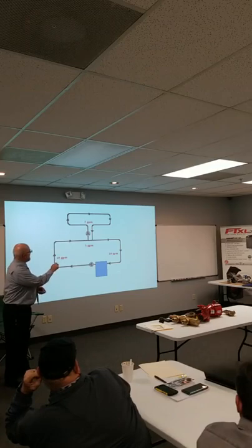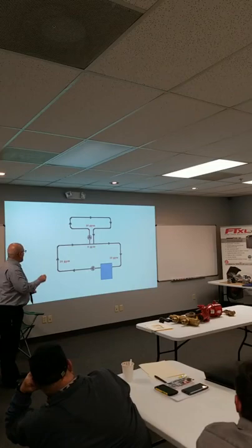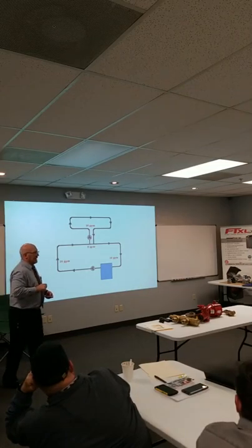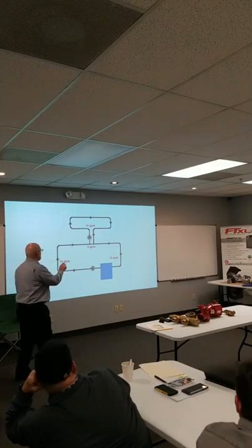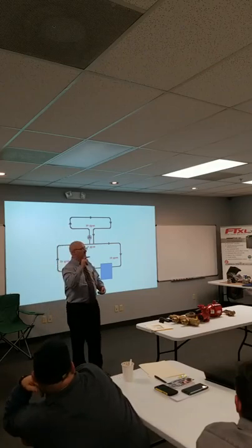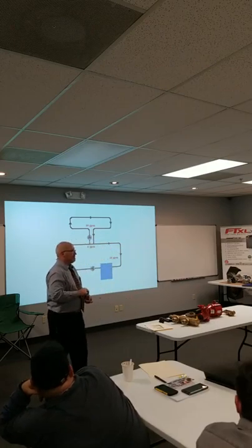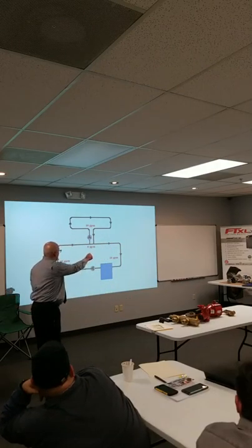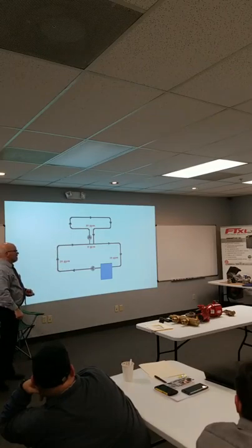And this mixes y'all up too, because now we're flowing this way instead of the other way. But anyway, this pump's pumping out, this pump's pulling that out, going through the system, injecting back in, okay? How about if I have a pump on this secondary loop that wants 10 gallons a minute? So now I've got 10 going through the primary. Oh boy. I take 10 gallons out, what's going between the tees? You can do this. Zero. Absolutely. Unless you've got other loops, and then they're going to be getting cold. Well, I'm still putting water back in if they're downstream of here. It just turns it into the same as a series type system, but only when both of them are trying to run the same.